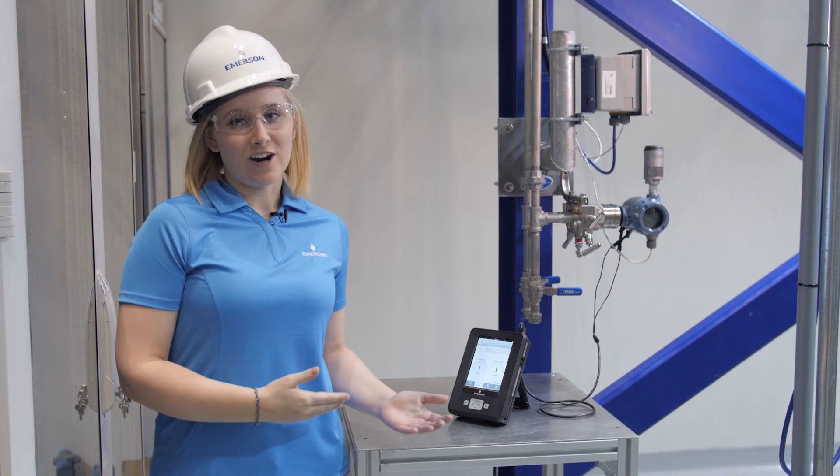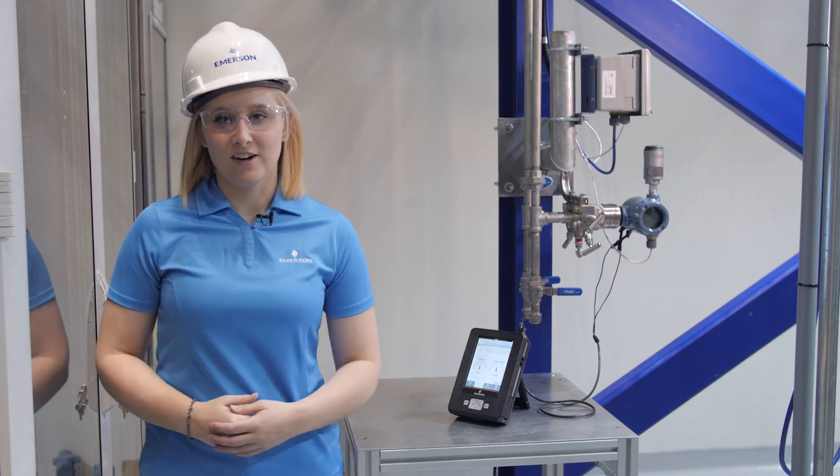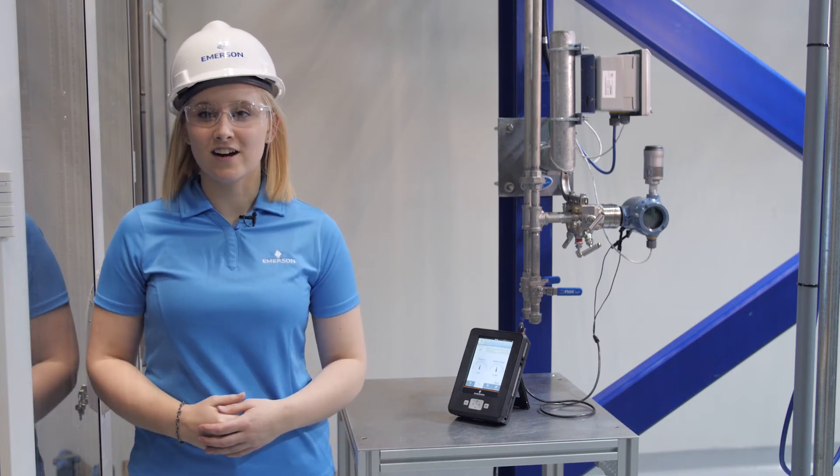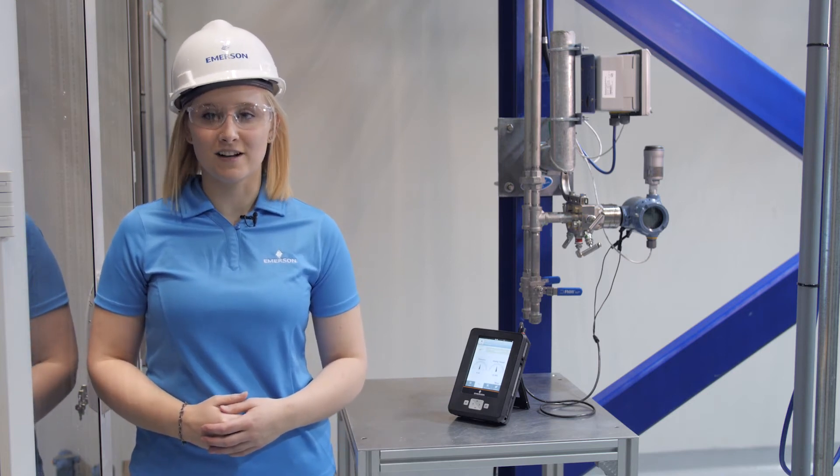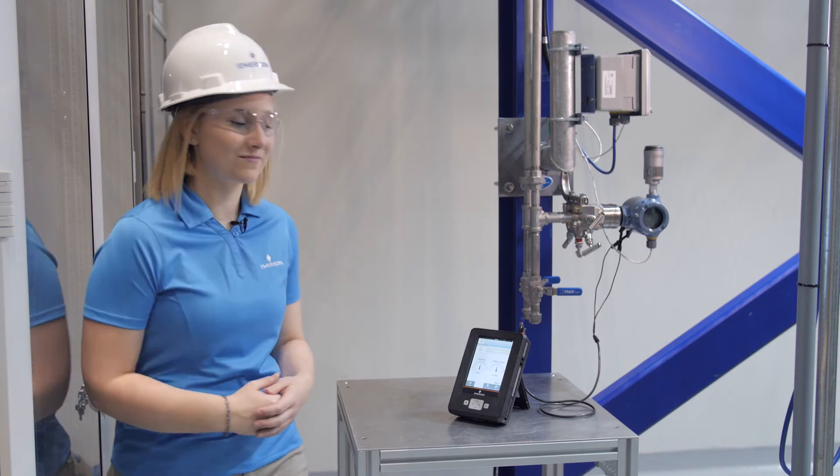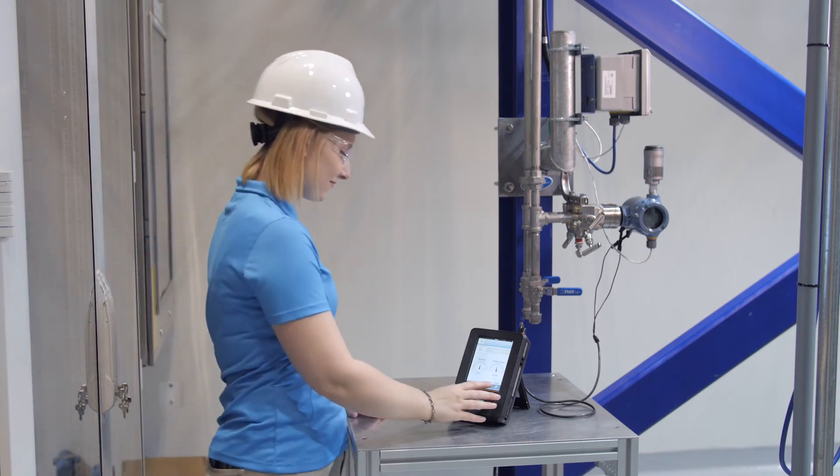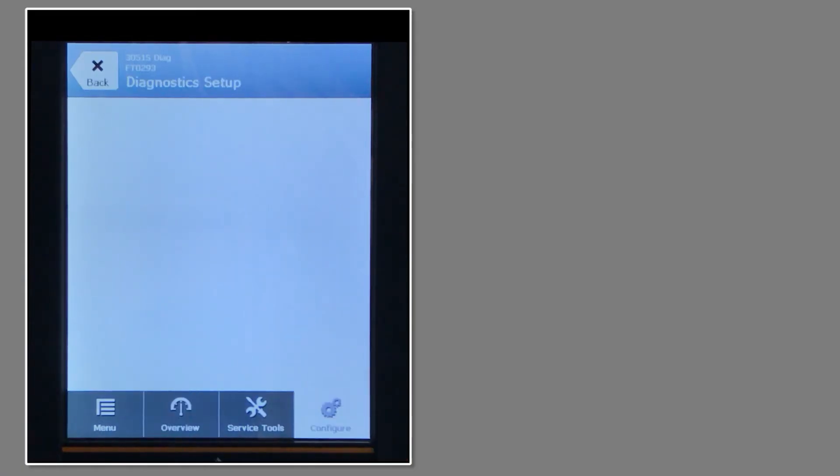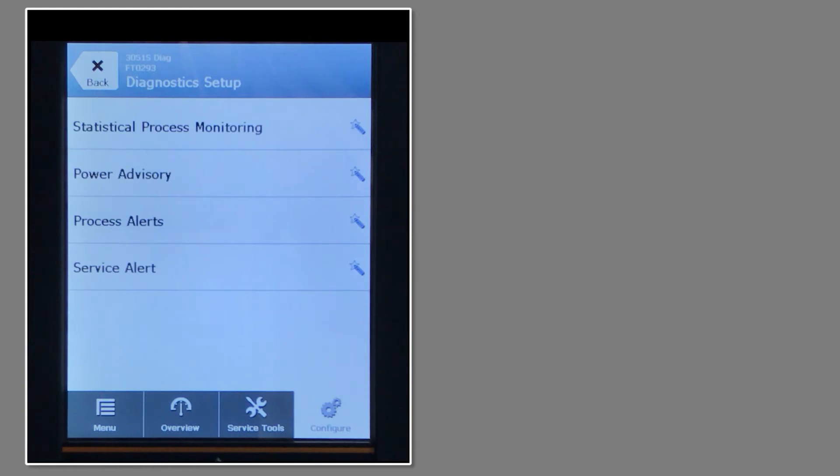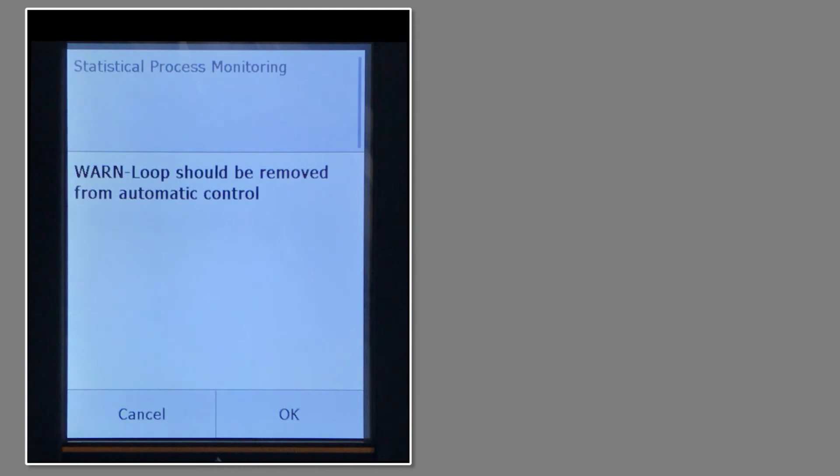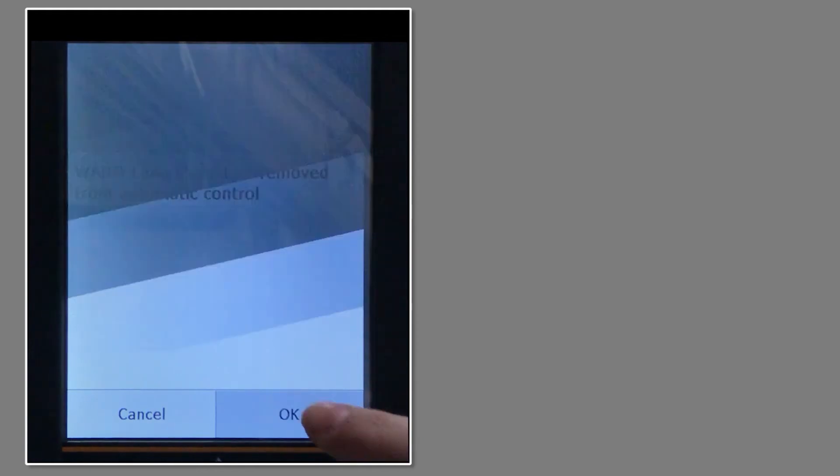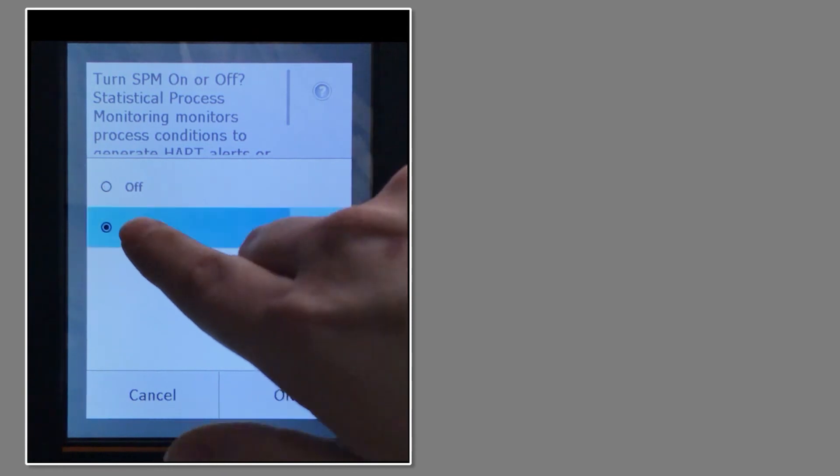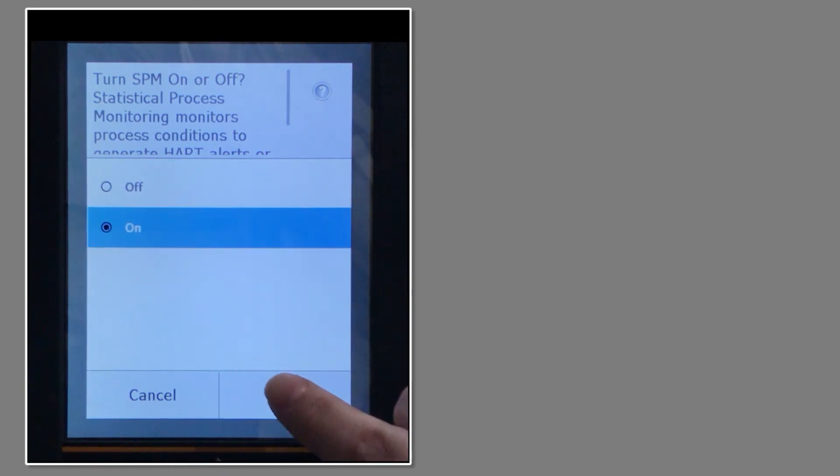Now that we have the Trex connected to the transmitter, the first step is to turn on statistical process monitoring or SPM. I'll do this by selecting configure, selecting statistical process monitoring from the diagnostic setup screen. This is a reminder that the transmitter you're configuring should be removed from process control. Select OK. And finally, turn on SPM and select OK.